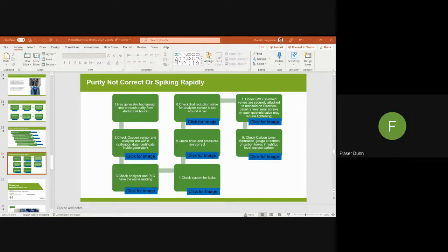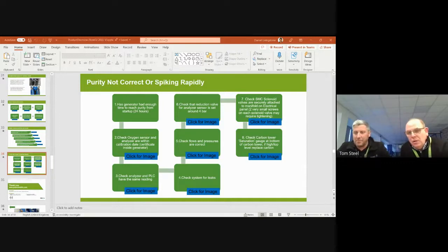Right, I'll take this. Guys, what I would say is you are more the experts on what is required by the patients. The system will give you purities from 90% up to 94%. Now that purity is usually set at installation, so we don't usually intend to vary that purity throughout the life of the generator. So in speccing the system, you will spec the purity required, and that will be factory set.